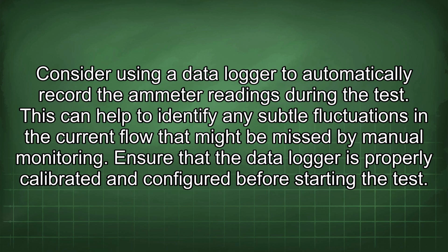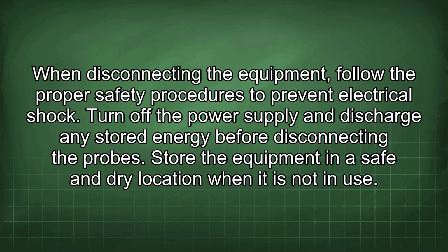Consider using a data logger to automatically record the ammeter readings during the test. This can help to identify any subtle fluctuations in the current flow that might be missed by manual monitoring. Ensure that the data logger is properly calibrated and configured before starting the test. When disconnecting the equipment, follow the proper safety procedures to prevent electrical shock. Turn off the power supply and discharge any stored energy before disconnecting the probes.